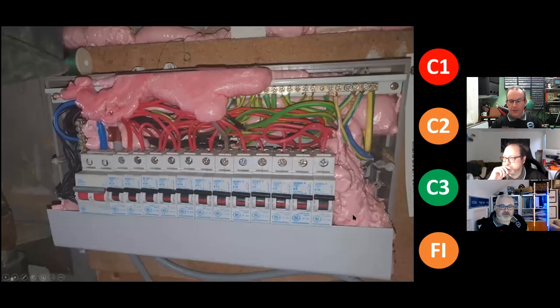Now, look at what's missing there. This was sent to me the other day, and we've got loads and loads of pictures. We could do a webinar just on insulation affecting consumer units. I've never, ever seen this in a consumer unit, where it's fairly evident somebody has pumped foam insulation in from one side and it's filled the board. And they're GE specials, these are Screwfix specials.